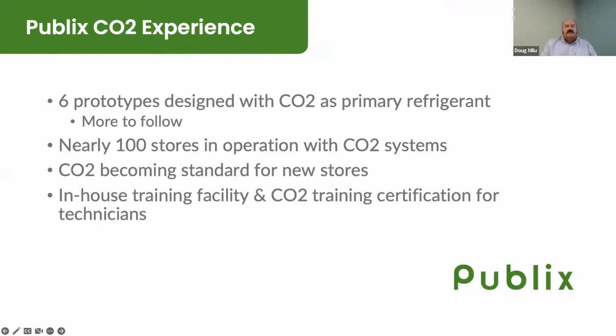The majority of our systems are what we refer to as liquid overfeed. So we have low temp CO2 DX refrigerant systems, as well as pumping 20-degree liquid CO2 throughout the entire medium temp cases on the sales floor.